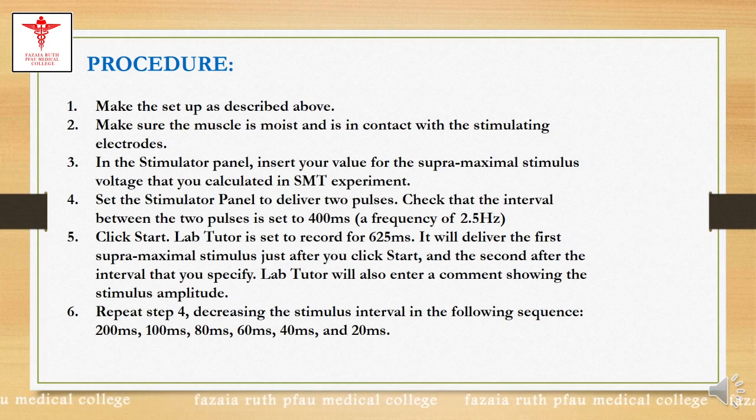Click start. LabTutor is set to record for 625 ms. It will deliver the first supramaximal stimulus just after you click start and the second after the interval that you specify. LabTutor will also enter a comment showing the stimulus amplitude. Repeat the step, decreasing the stimulus interval in the following sequence: 200 ms, 100 ms, 80, 60, 40 and then 20 ms.